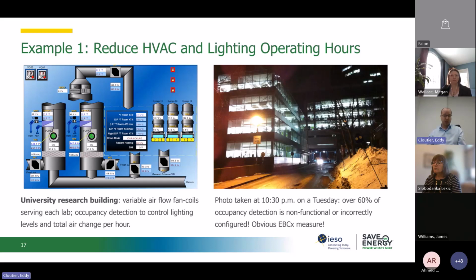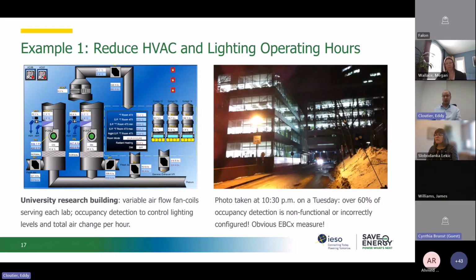So during the recommissioning project, we discovered that more than 60% of the occupancy sensors were either non-functional or incorrectly configured. The result, as we can see in the picture on the right, is that both the lighting and the amount of air change in the lab remained unchanged even during the night. So, of course, the very simple existing building commissioning measure consisted of reconfiguring all the occupancy sensors and making sure that the sequence of operation was as the design intention was. So it generated a lot of energy saving, of course.